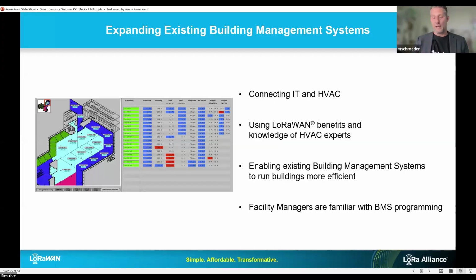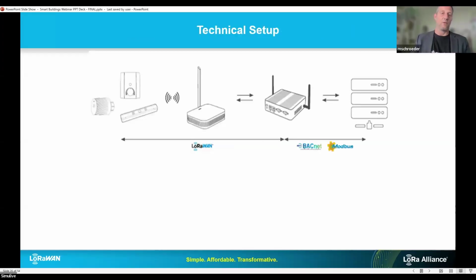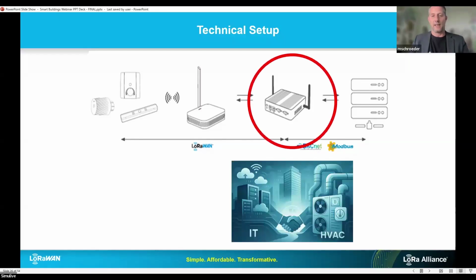This sounds very complex, but let's look at a general setup for a retrofit project. When we look at the technical setup, first we install the sensors. The sensors send data to a gateway, and the gateway forwards it to a converter. The converter is more or less the game changer in these projects, where we have to integrate LoRaWAN data points into an existing building management system.